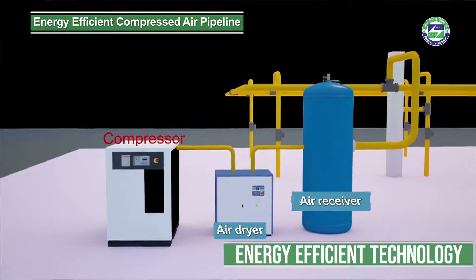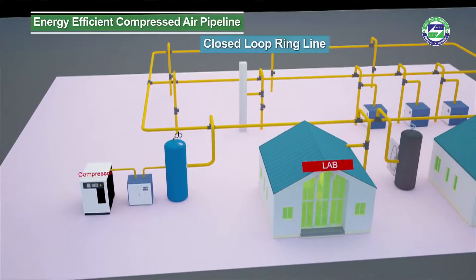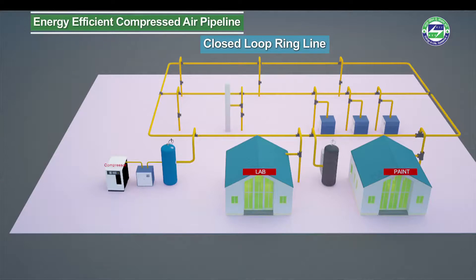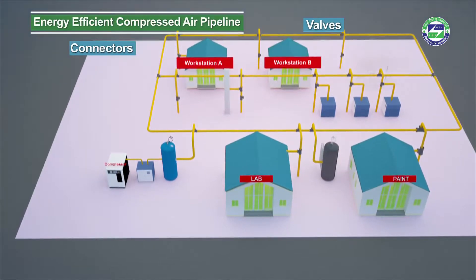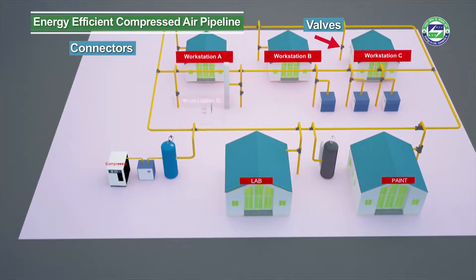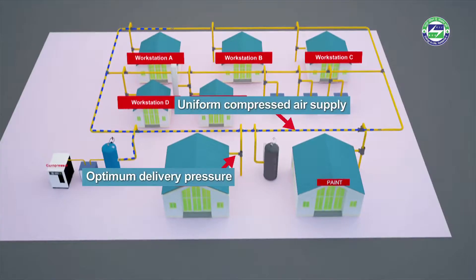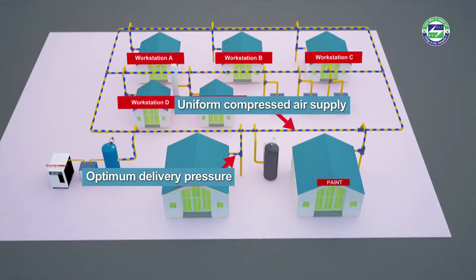The ring main system is an energy efficient alternative in piping. The design includes a closed loop ring line along the area where compressed air consumption takes place. Branch pipes connect the loop to various consumption points, providing uniform compressed air supply despite heavy intermittent usage.